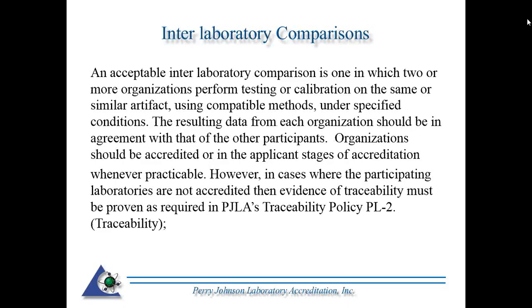Now let's take a look at interlaboratory comparisons. So what is an interlaboratory comparison? An acceptable interlaboratory comparison is one in which two or more organizations perform testing or calibration on the same or similar artifact using a comparable method under specified conditions. The resulting data from each organization should be in agreement with that of the other participants. Organizations should be accredited or in the applicant stages of accreditation, whenever practical.